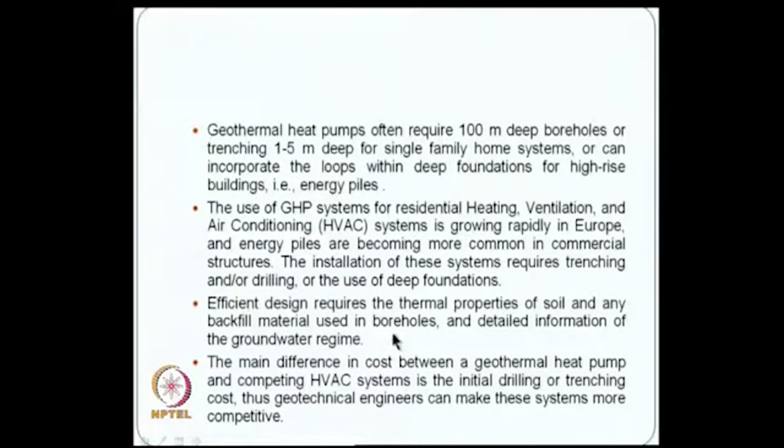So, as I just mentioned, clays and sands and varieties of materials have varieties of thermal properties, and one needs to understand the thermal response of these materials, and also have detailed information on the groundwater regime. The main difference in cost between a geothermal heat pump and the competing heating, ventilating, air conditioning systems is the initial drilling or trenching costs, and thus geotechnologists can make the systems more competitive.